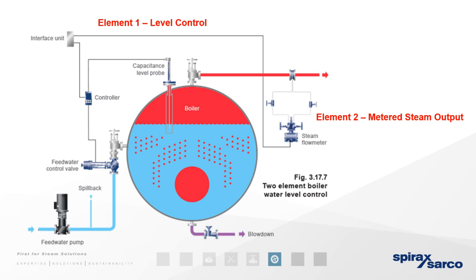So one element control and 2 element control. As you can see here, 2 element control is level control and metered steam output, and suitable for sudden load changes. So if you have a high demand, plus or minus 25% change, this would be the best system to use. So as you can see, you have your capacitance probe here, your controller for your feed water. Element 2 is your metered steam, and that's going back to an interface unit, which is both receiving and telling the feed pump to react. Are there any questions on that?